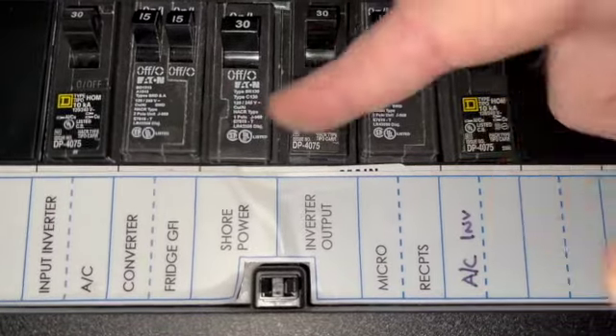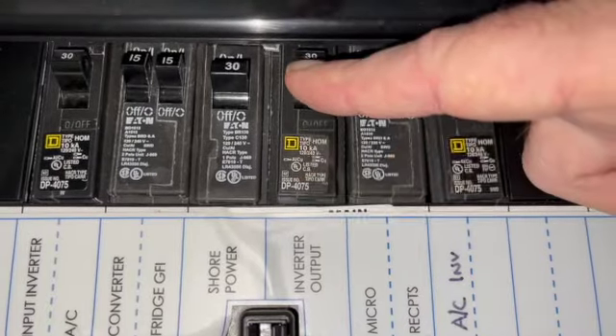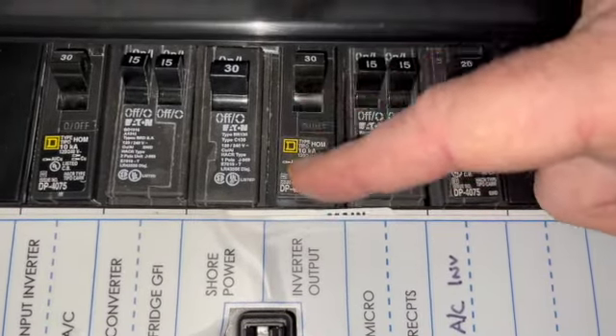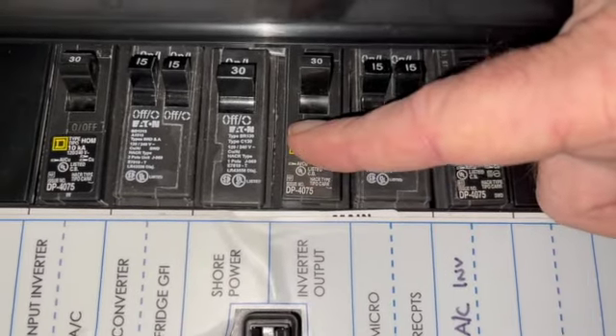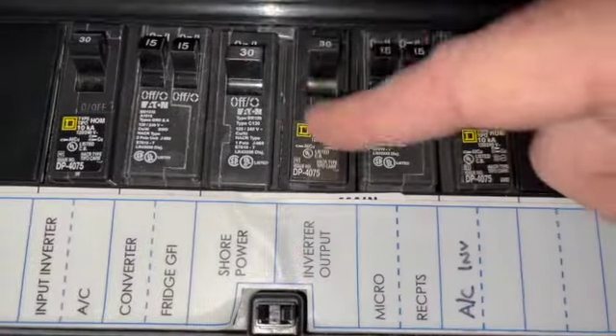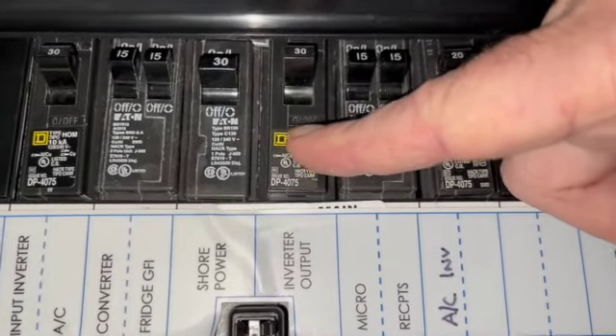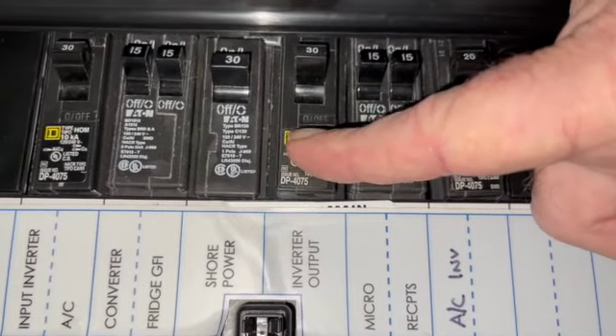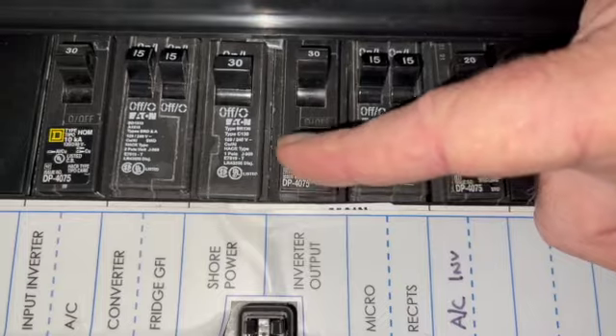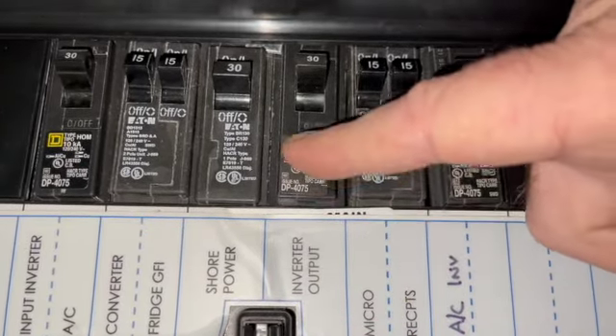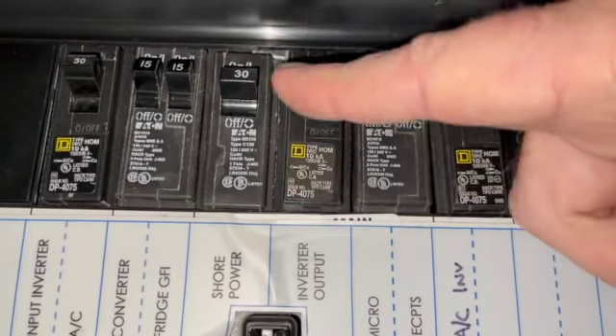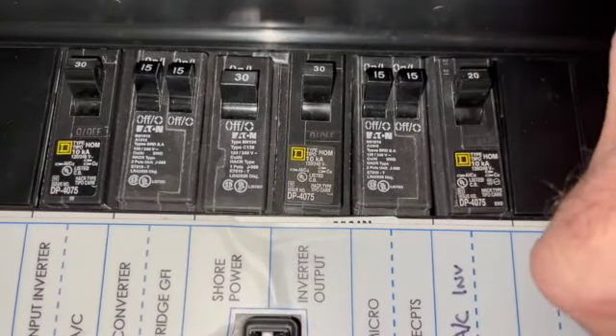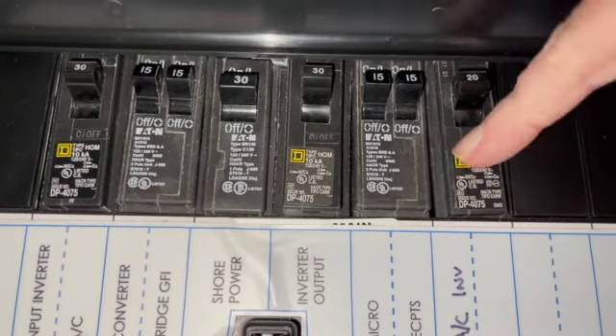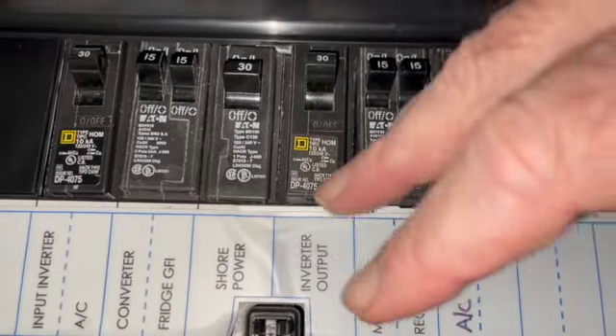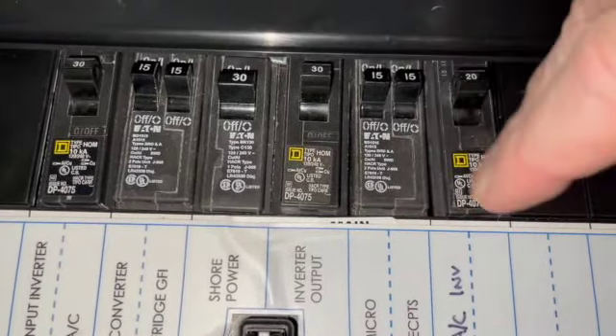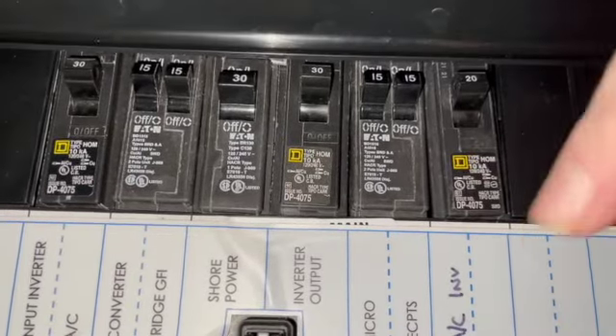The other thing I did, of course, once I did that, I figured I might as well go ahead and upgrade the service. This was a 20 amp output of the inverter, limiting it to 20 amps. So I went to the full 30 amps that the wire can handle. Remember, you want the breakers to match the wire capacity, not necessarily what you're trying to run on it. The wires I put in here were capable of 30 amps. They're 10 gauge wires, so it's safe to do. And now I can use the full capacity of that 3,000 watt inverter output, so I can run the air conditioner, which actually runs less than 20 amps AC, and I can also run the microwave along with the air conditioner.